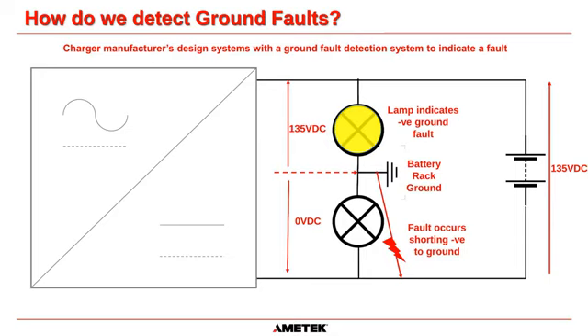And the exact same happens the other way. If you have a direct short between negative and ground, if you go between negative and ground with your Fluke, you're going to get 0 volts DC. If you go between positive and ground with your Fluke now, you're going to get 135 volts DC, and this lamp will go bright and this lamp will go off. So that is the most basic form of ground fault detection, and that is why the ground on your DC system is going to be roughly halfway between the positive and negative.